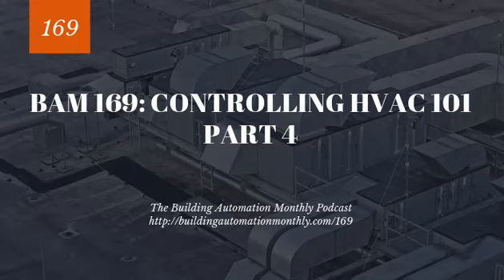It's a lot easier to put your meter on a 2-pair and say, these 2 conductors, I'm metering them, they have 2 volts DC, whatever, or they don't, versus trying to figure out what's going on with MSTP, especially with a system that's responsible for the heat of the entire building.